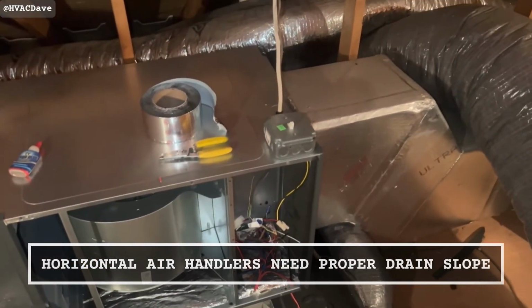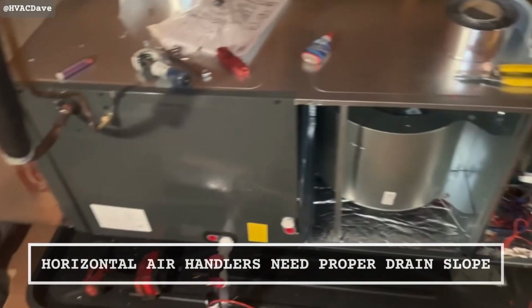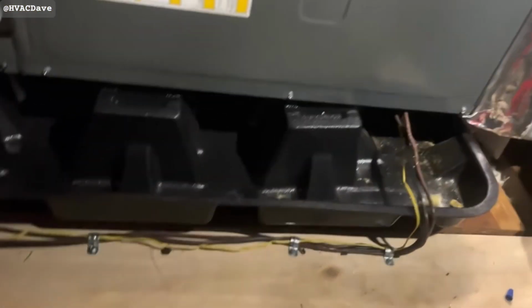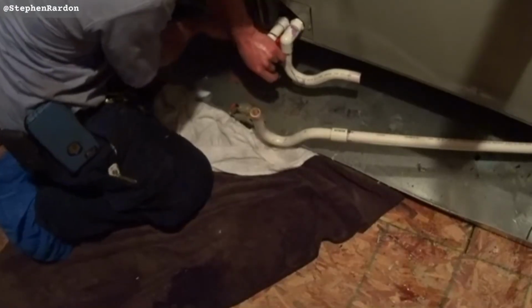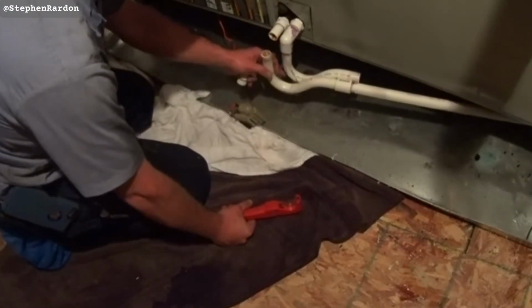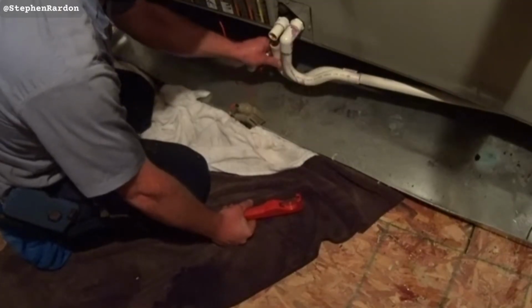Number 30. Horizontal air handlers, the kind that lie on their side in attics, need the drain pan checked for slope. Code requires the pan to drain toward the outlet. Settled framing or a unit installed slightly off level lets water pool at the wrong end of the pan, which rots the metal and eventually drips through the ceiling below. 20-second check with a torpedo level. If the pan tilts away from the drain, shim the unit.